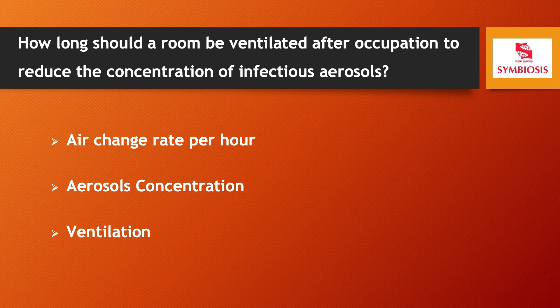So, in order to reduce the contaminant concentration to 1% of its initial concentration, a room should be ventilated for more than 9 hours at an air change rate of 0.5 air changes per hour, or for about 1 hour and 10 minutes at an air change rate of 4 air changes per hour.